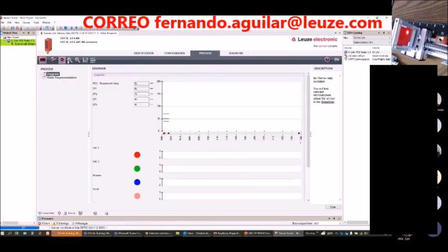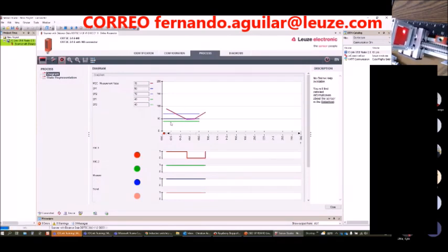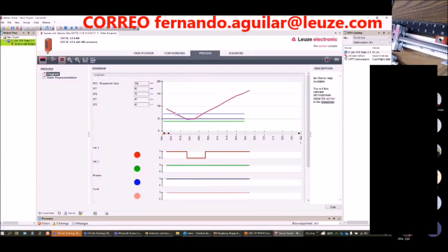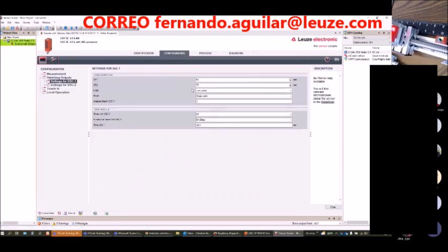You always have to press play if you want to get the process data showing on the diagram. There you see the bit change. So let's say I want to change, I don't want my target to get 40 millimeters away. I want it to change directions when it's 80 millimeters away. So I could stop this, go to the configuration, and set this to 80.